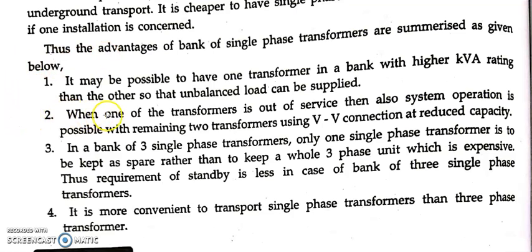So even for unbalanced load, you can connect two different kVA rating transformers so that they can supply the unbalanced load. It is possible. Usually what happens, if I want to connect a bank of single phase transformers, in that case we need to have all the transformers of the same rating. But if you want to connect two transformers, I can connect two different kVA rating transformers so that unbalanced load can be supplied. That is the advantage, but it is not true for your single three phase transformers.